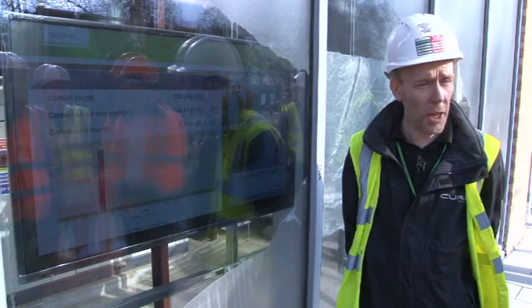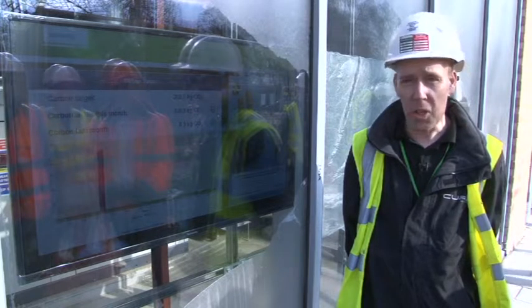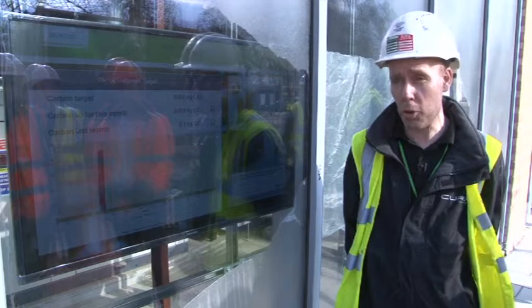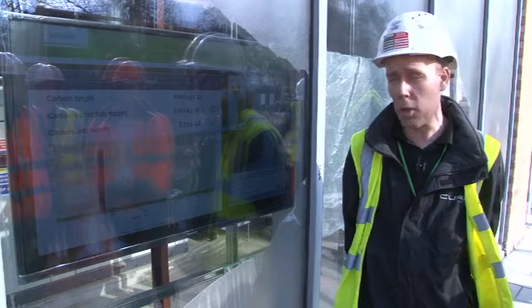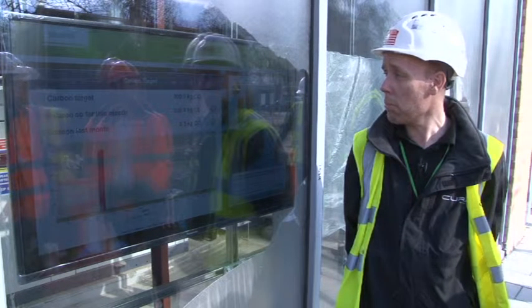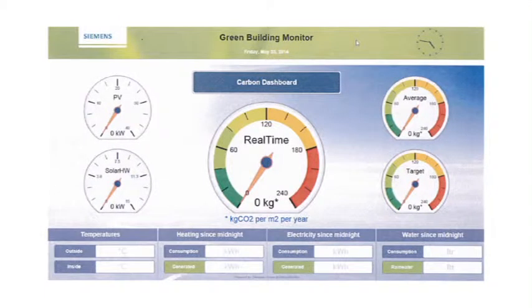This is the green screen energy display for the educational purposes of the plant room. It currently consists of 6 slides containing information on the CO2 used, CO2 produced by the building, the energy, the water and the gas used by the building, and an overall summary of the state of the green credentials of the building. Other benefits with this are, at the moment we are currently scrolling a message which just tells you what the outside air temperature is.